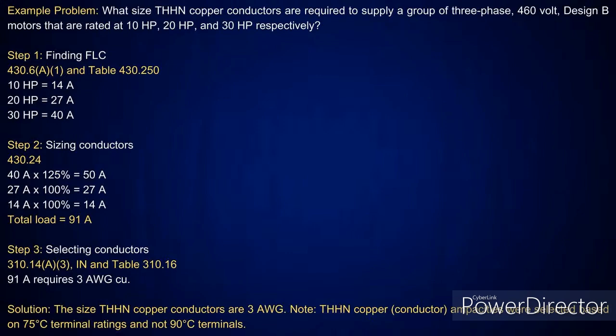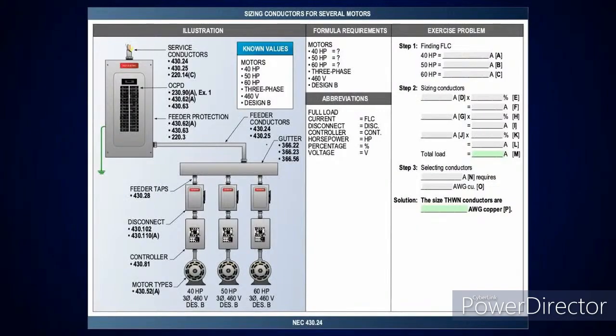No, and it brings up one question that I want to ask though. Are single motors always calculated at 125%? Is there any case where you could just take a single motor and calculate it at 100%? Like if it was intermittent duty or something, maybe. But I don't know, that's the only thing you would get into. You'd be looking at table 430.22(E) that gives you periodic, intermittent, and those things. That's the only place I know that you would get away with that. As a matter of fact, we'll show that here in this presentation. All right. Okay. Awesome.